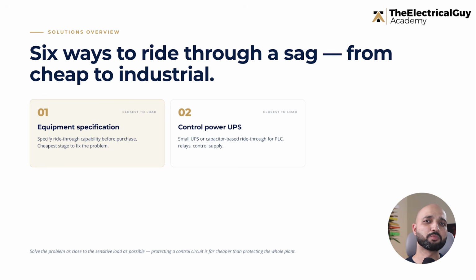So, providing a small UPS, DC power supply backup, capacitor-based ride-through module, or control transformer support can help. This can prevent unnecessary tripping during short interruptions. But UPS selection should be done carefully. For small control loads, this is often one of the most practical solutions.